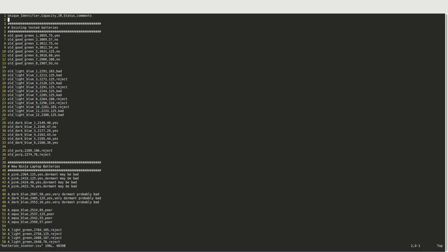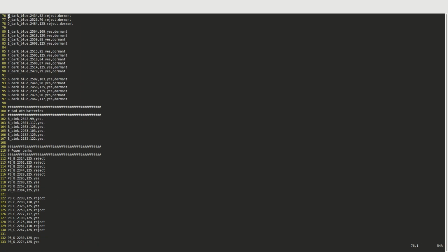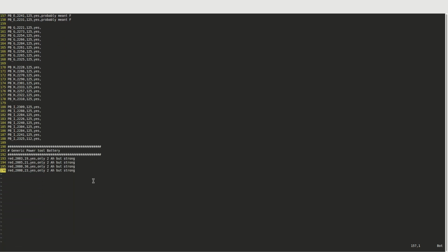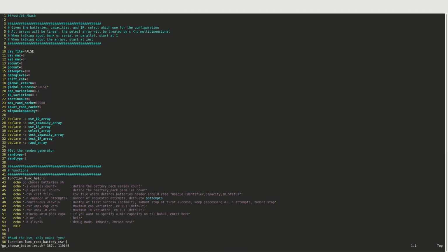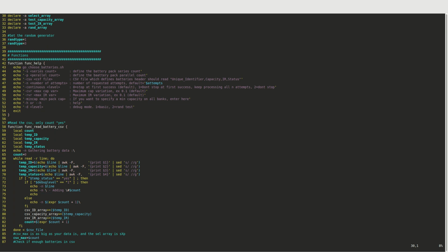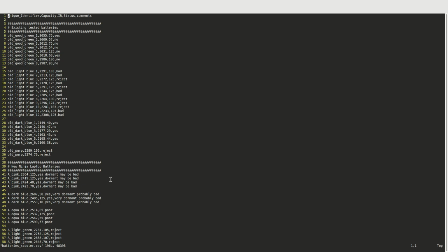So you reject all the ones that are no good, and you end up with a whole bunch of batteries. Here we have about 196 batteries, and if they pass, they're saved. I wrote a script that goes through the spreadsheet, takes a look at all the information, and selects. For example, you don't want all the batteries on one bank super high and another bank lower. You need it all balanced. You want a battery pack that's balanced in both capacity and internal resistance. So I sum the capacity but average the internal resistance, so all banks have the same average internal resistance and roughly the same capacity based on your criteria.